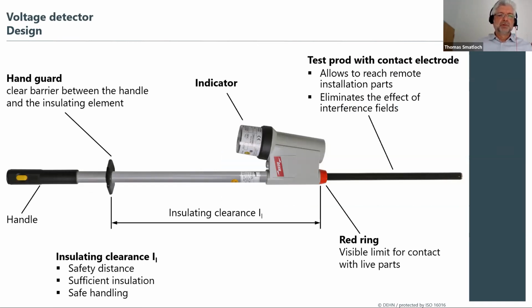That is due to the fact that it is possible to put an extension in, depending on the size of your switchgear cabinet where you want to use this device. And then again, we have the hand guard, where the hand should always be behind it to have sufficient isolating distance to the probable live parts. Here you check that the voltage is really switched off. And between the handle and this red ring, we have the indicator showing if voltage is present or not.